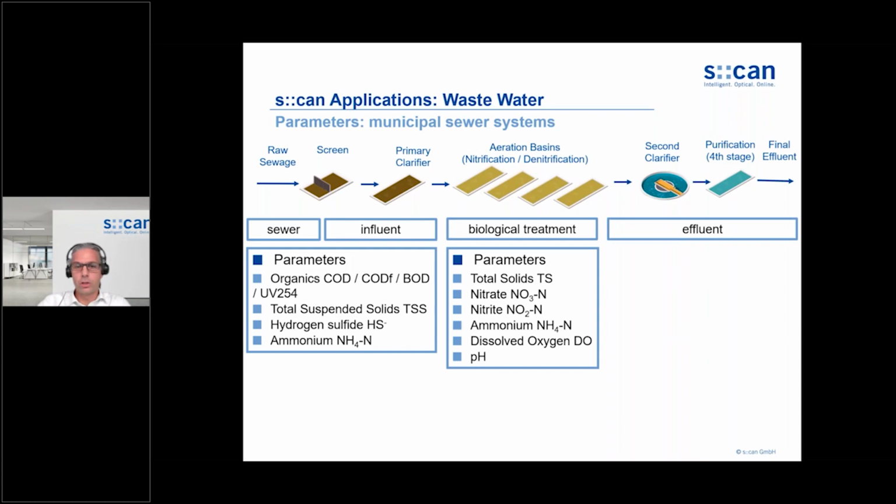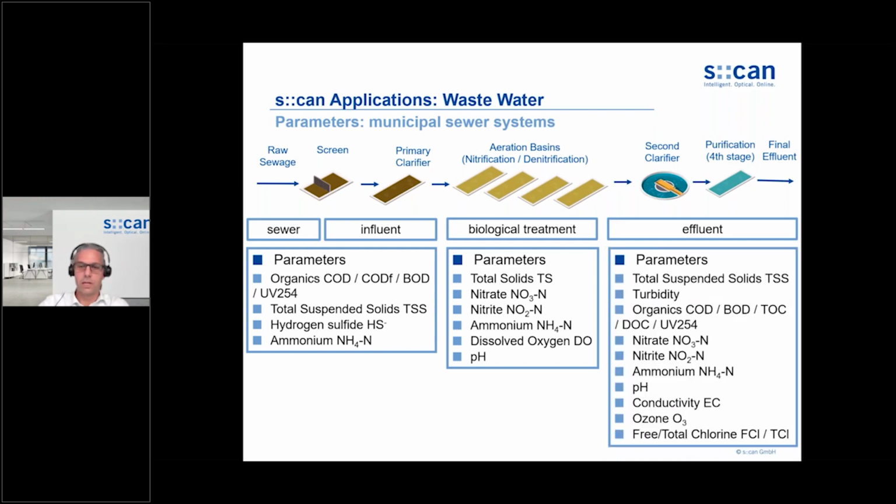After the biological treatment, the second clarifier and sometimes also an advanced treatment, the so-called fourth stage treatment, takes place before the wastewater is released to the rivers. Typical parameters monitored here are solids or turbidity, organics again, nitrate, nitrite, ammonia, all the species of nitrogen, pH, conductivity, and if there is a disinfection, also ozone and free and total chlorine are commonly monitored here.